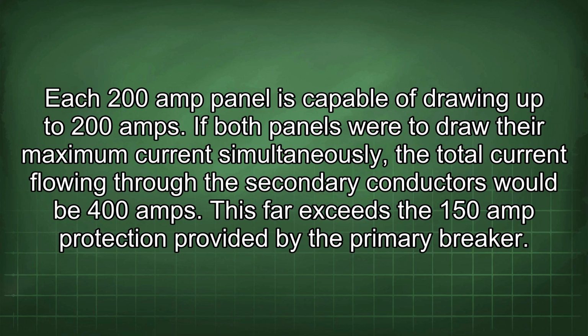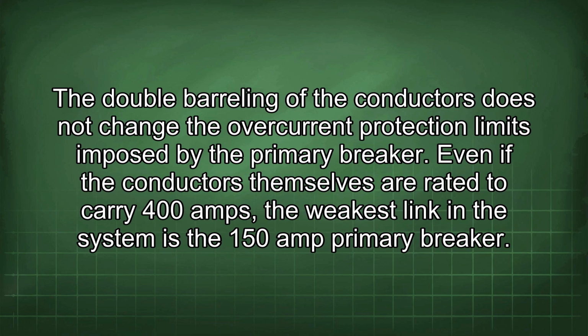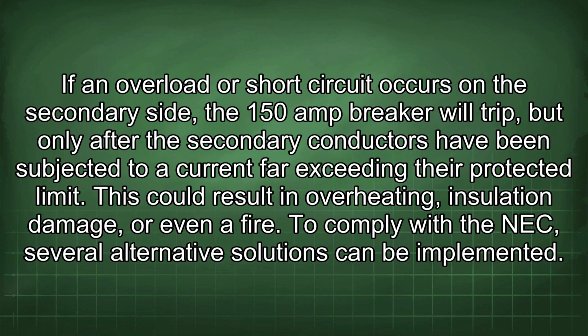Each 200-amp panel is capable of drawing up to 200 amps. If both panels were to draw their maximum current simultaneously, the total current flowing through the secondary conductors would be 400 amps. This far exceeds the 150-amp protection provided by the primary breaker. The double-barreling of the conductors does not change the overcurrent protection limits imposed by the primary breaker. Even if the conductors themselves are rated to carry 400 amps, the weakest link in the system is the 150-amp primary breaker. If an overload or short circuit occurs on the secondary side, the 150-amp breaker will trip, but only after the secondary conductors have been subjected to a current far exceeding their protected limit. This could result in overheating, insulation damage, or even a fire.